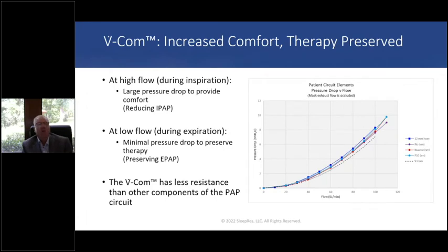How does it work? Well, we've already talked about this. At high flow during inspiration, there's a large pressure drop, and that produces comfort. VCOM right now is really the only way to reduce IPAP. I mean, you could manipulate the system in other ways, but no ventilator, no BiPAP, no CPAP can lower IPAP below EPAP. None of them can in the world currently.